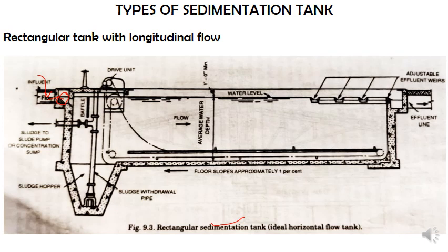Once the water enters through this inlet arrangement, you can see there will be a baffle. So why is this baffle provided? So that the inflow water should not disturb the water which is there in this particular tank. As and when it hits the water, the water will go down and then try to move in the horizontal direction. As it moves in the horizontal direction, the settlement of particles is bound to take place.